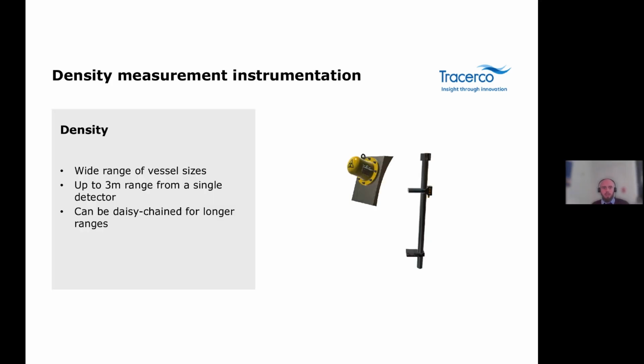The density measurement utilizes scintillation technology, and this technology in this application means we can use a smaller source size with a higher sensitivity detector, which allows for much greater accuracy in density measurements. These can be used to control and monitor interfaces and densities. A single detector can cover up to 3 meters of range, or for a longer application, multiple detectors can be daisy-chained together. The product has an inbuilt relay or analog output, and it does not require any hardware in the safe area, making the installation very smart and easy.